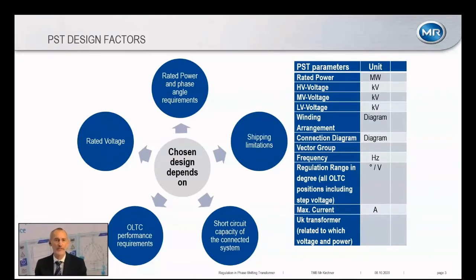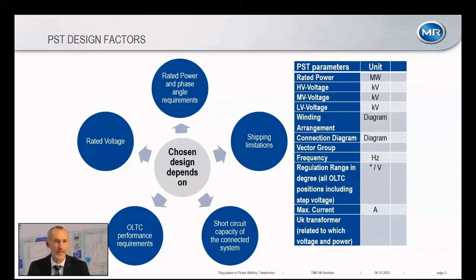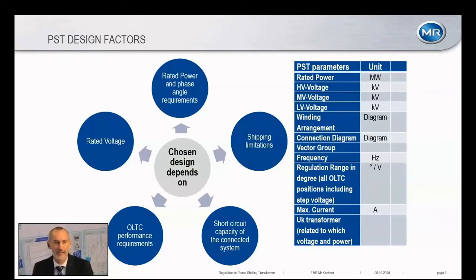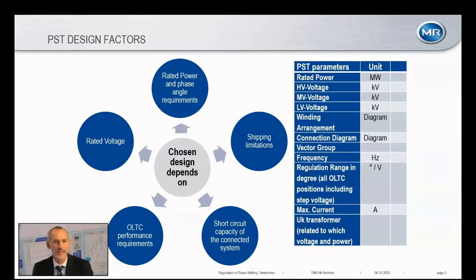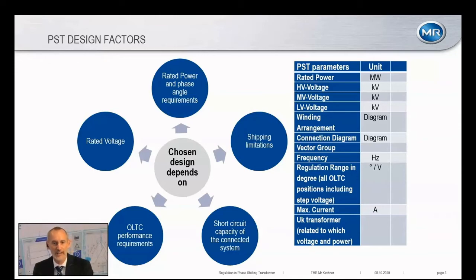When thinking about phase shifting transformers, we start with rated power — not different from any other transformer. But then comes the phase angle: we're talking about an angle in degrees and how many steps are needed to realize a certain angle, which is different from normal transformers. Rated voltage of the system line is important, and in many cases PSTs are very large equipment that must be shipped worldwide. Shipping limitations — especially when leaving waterways for railway or road transport — can cause significant problems that must be considered.